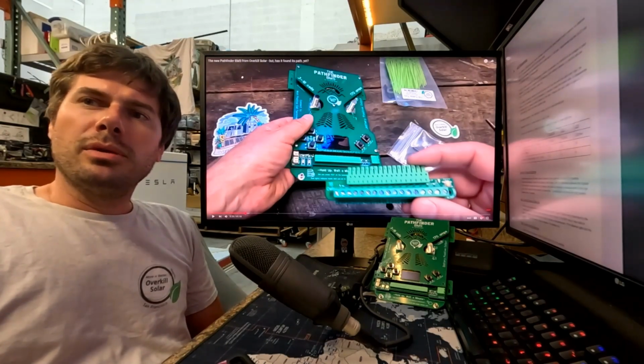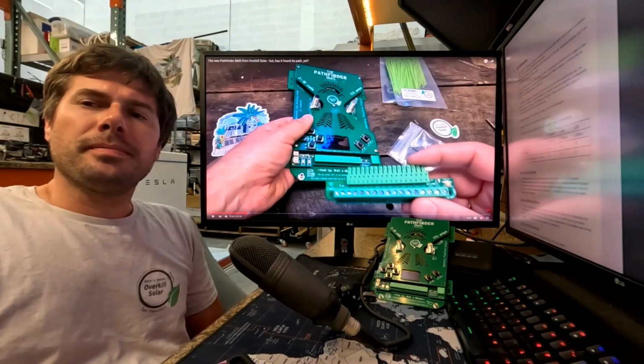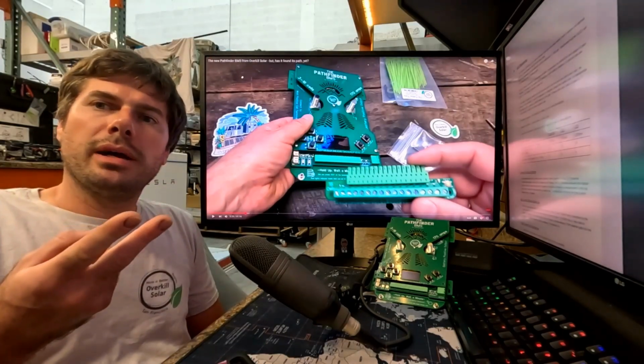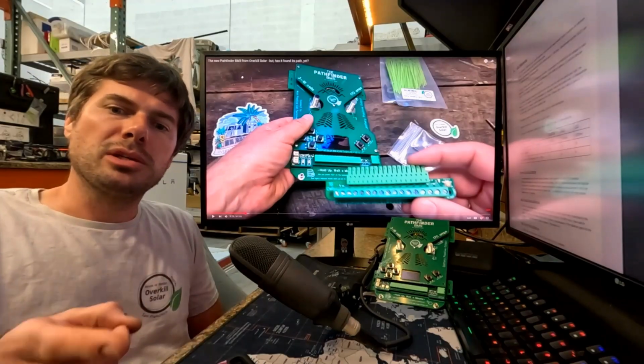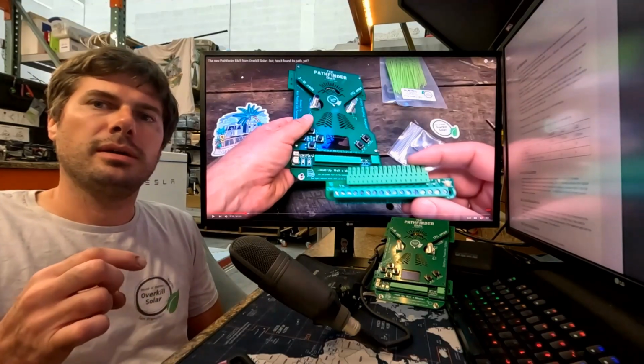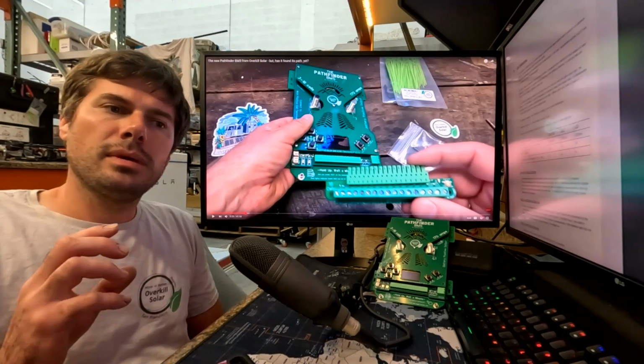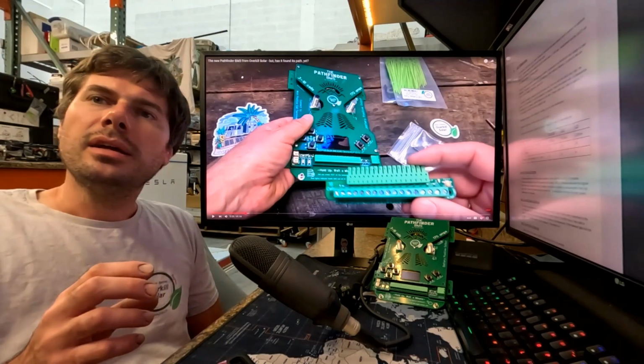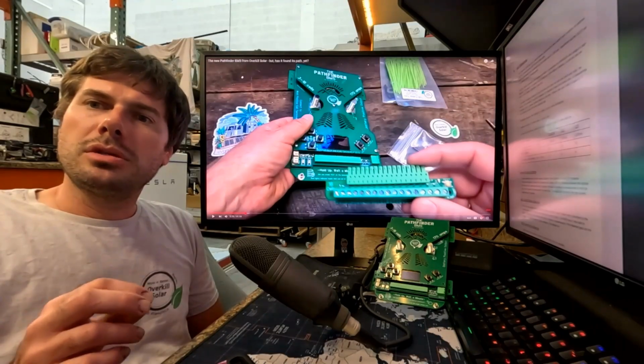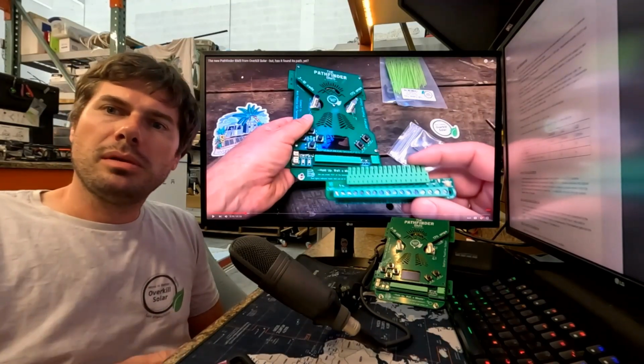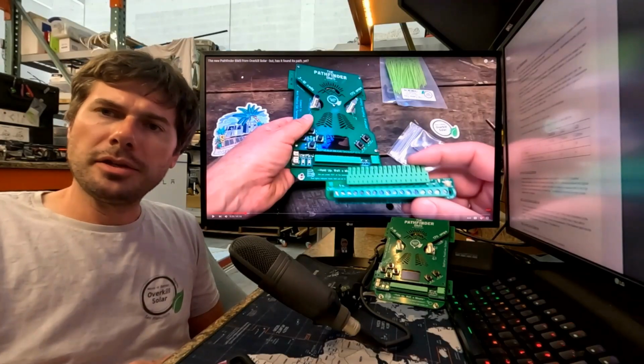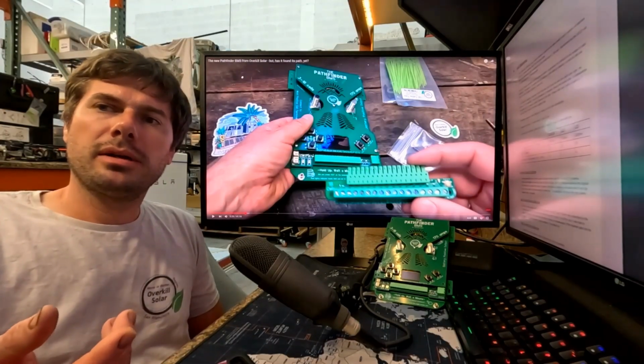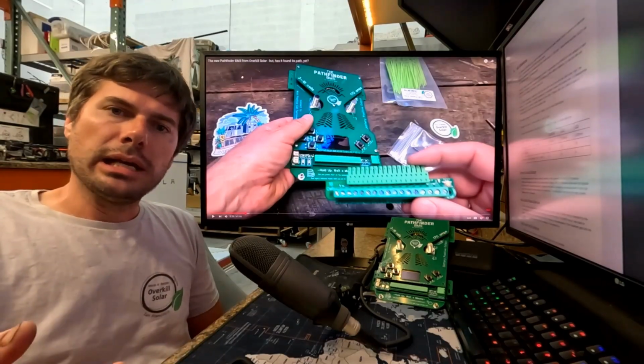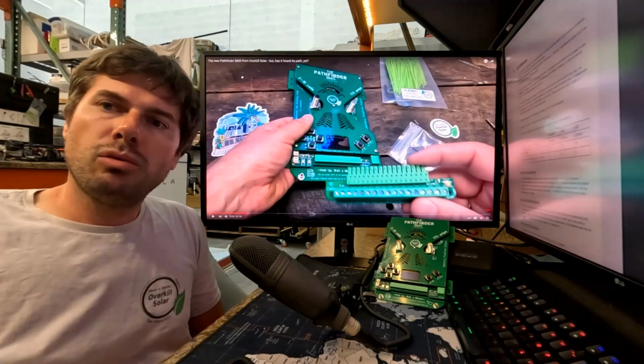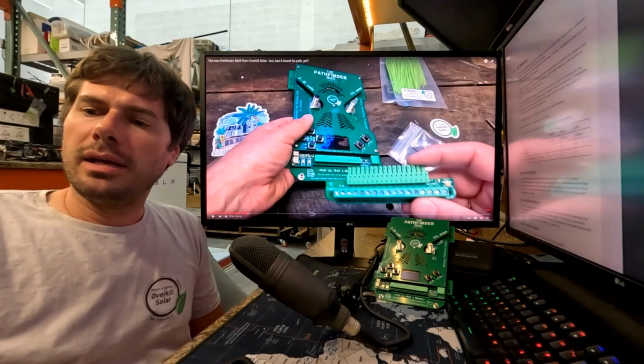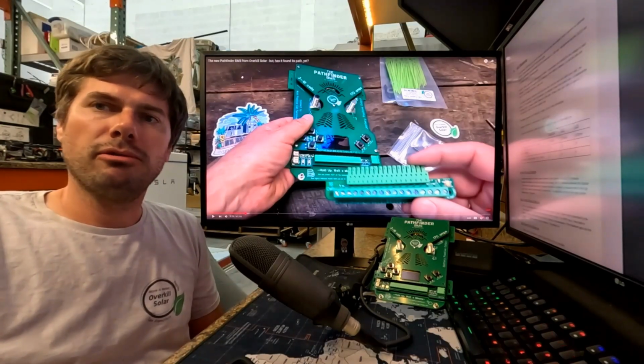The only thing that really can't be fixed is swapping balance wires, so you'd have a negative voltage between two cell voltage inputs where they're just not protected against that. The solution we found was this simple indicator circuit on the terminal board. So if you have balance wires connected out of order where there's a negative voltage, the corresponding red light will come on, and you know to go back and fix that before you plug it into the BMS.